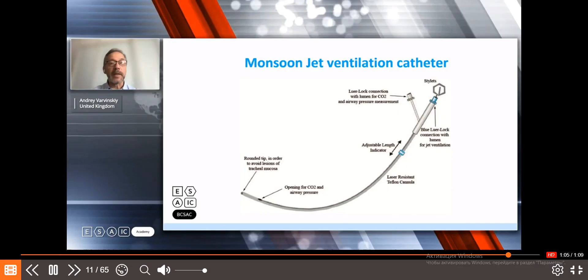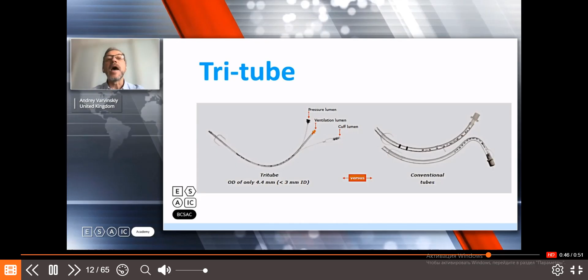And that is a tri-tube. This is the latest invention that comes together with a machine called Evone that we will touch upon a little later. And this tri-tube, as you can see, has 3 lumens. There is a cuff as well. So there is a lumen for the cuff, there is a pressure lumen, and there is a ventilation lumen. And you can see the difference between the conventional tubes and this tube. It's only 4.4 millimeters external diameter and less than 3 millimeters internal diameter. So you can see that a passive expiration will not be possible through that tube. So that needs a very clever mode that provides an active expiration. And there's only one machine in the world that can do that. I'll show you later.